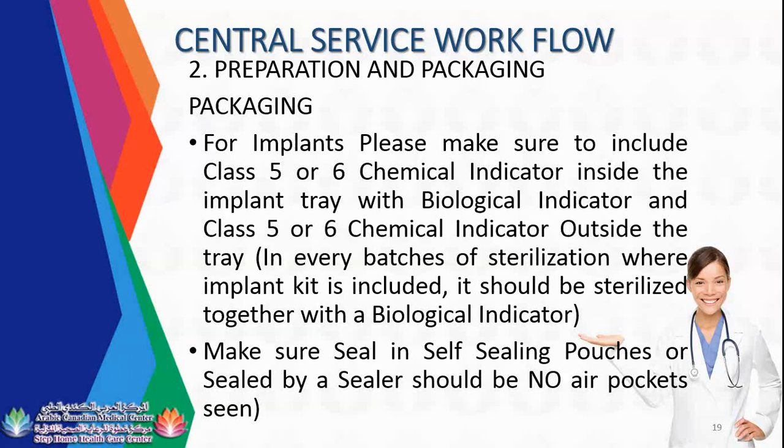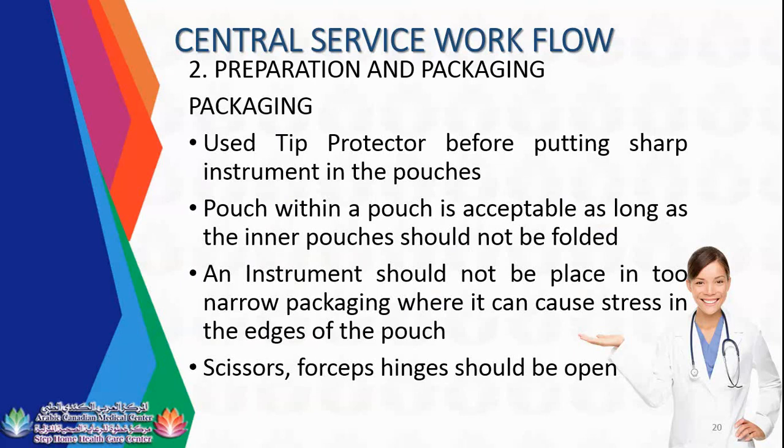So make sure seals in self-sealing pouches or pouches sealed by a sealer should have no air pockets seen. Air pockets, in simple terms, means there's no fold in your pouches. Once you seal the pouches, it should be plain as if it is ironed. So there's no crumple, there's no folding. Because if there's a fold in your sealing area, it can let contaminated air enter to the instruments, and it will cause the instruments to be unsterilized.